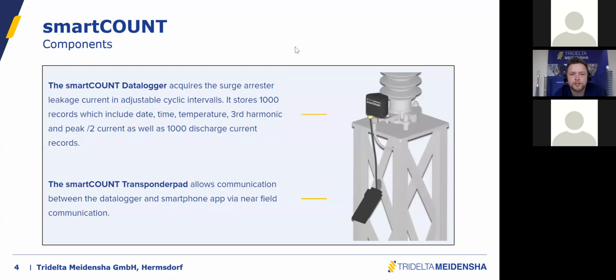The main components are the data logger. This is where the whole measurement takes place and where the data is stored before they are picked up. And we have the possibility to store 1,000 records for leakage current and 1,000 records for discharge current. And yesterday we had the question, what happens afterwards if the 1,000 records are full? Of course, we can go on measuring, but it will start rewriting the first, let's say, memory cells. This is what we call cyclic buffer.